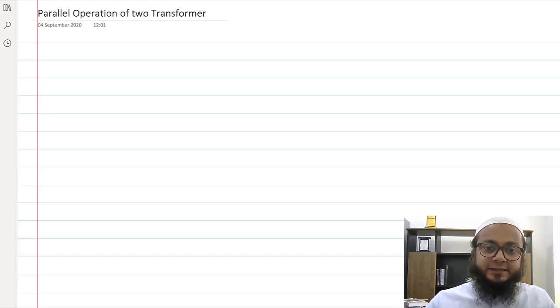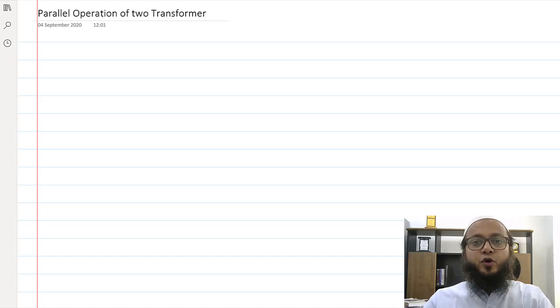And let's say if I replace the entire transformer with a new one with higher capacity, obviously then this process will take a lot of time as well, right? And even then what would be the use of that transformer which was already in use? So the one solution is to connect the transformer in parallel with this existing transformer. Okay, so connecting transformers in parallel means input supply is common for both the transformers, and even the load is common to both the transformers. Okay, so that is what we will discuss today.